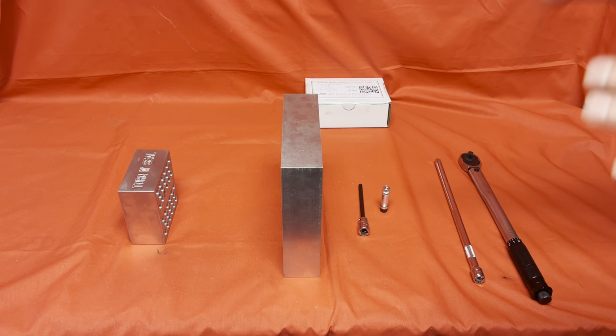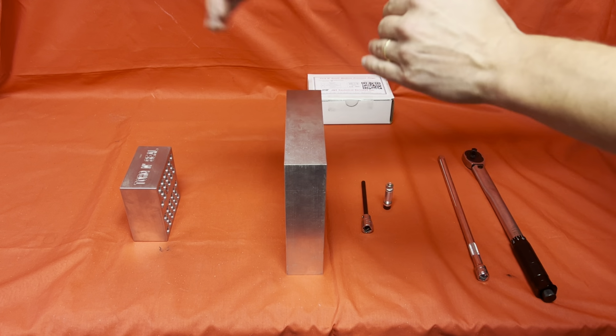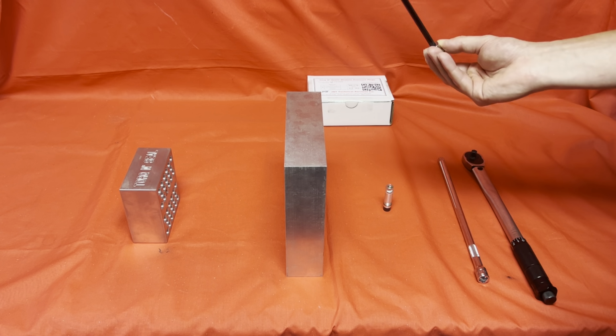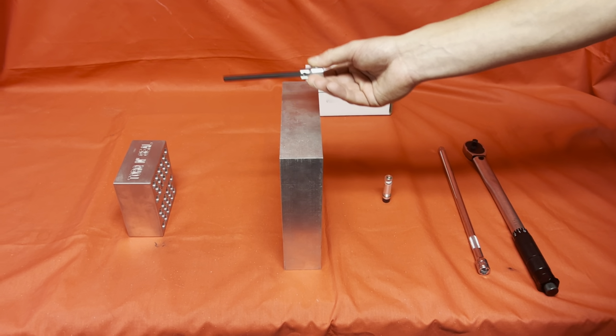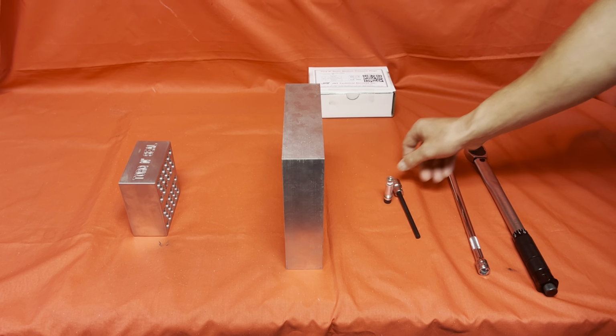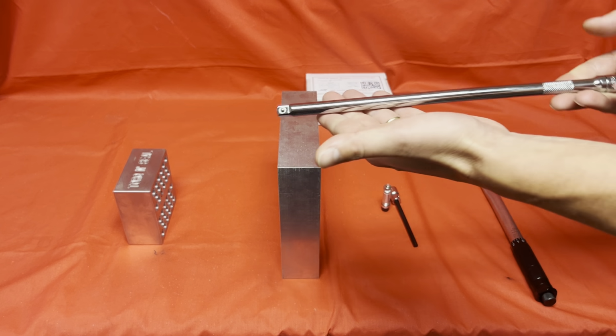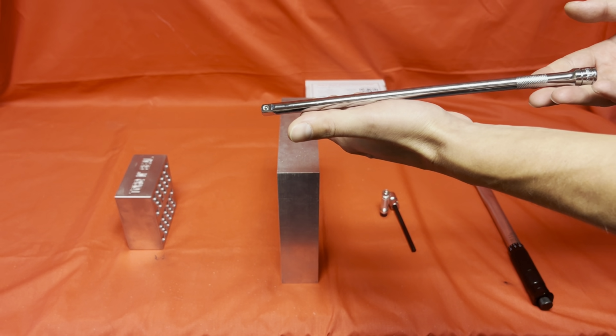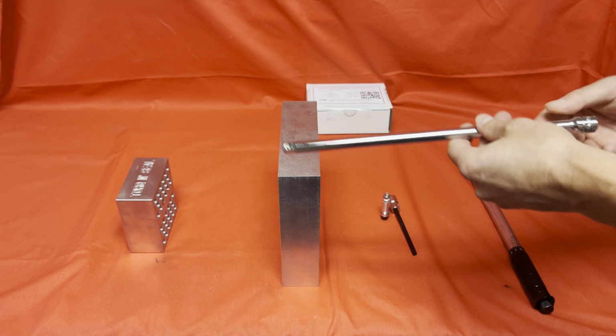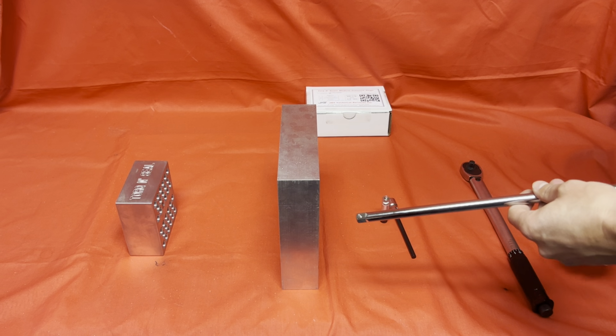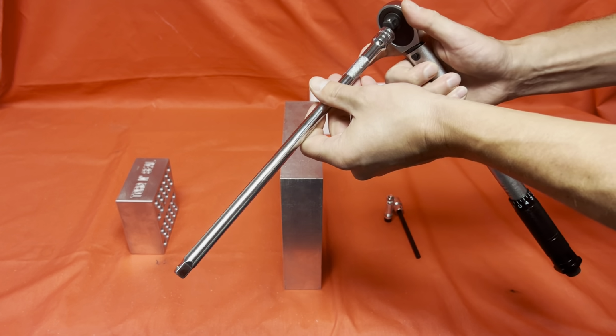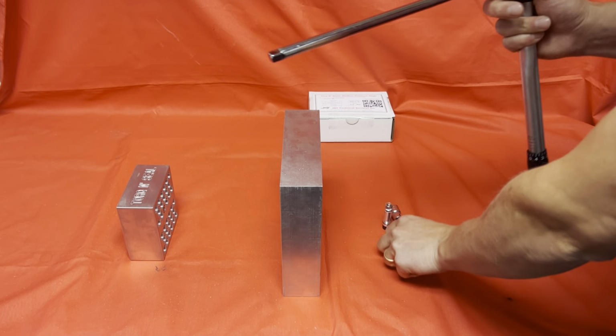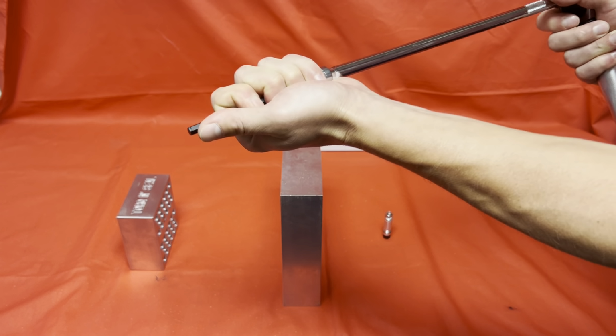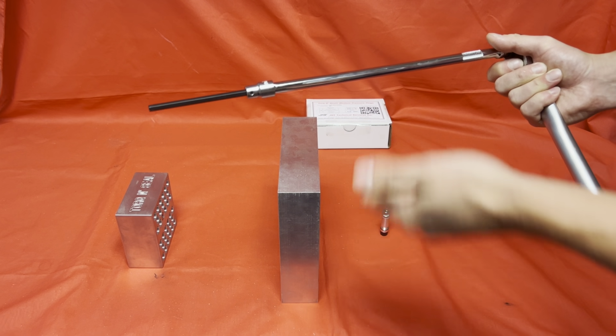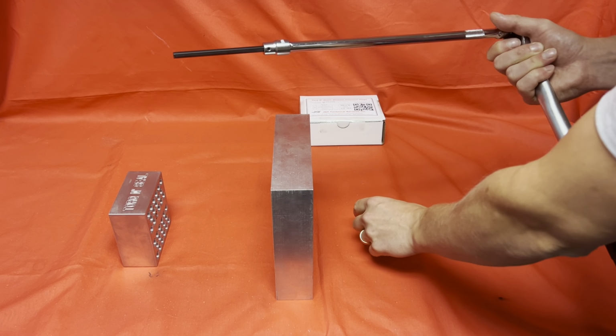The next thing about an air-cooled heat exchanger is you have a gap here. So your standard hex capture driver is not able to reach the tube sheet. So what we need to do is use a standard 3/8 inch square drive extension in between our torque wrench and our hex capture drive. So I'll go ahead and get that set up. And now I have a much longer installation tool, yet everything's going to work the exact same way.